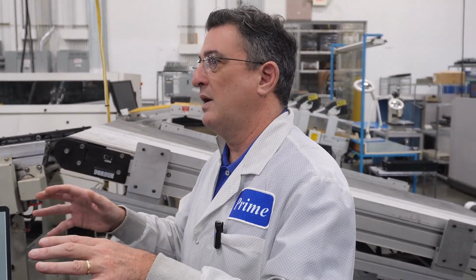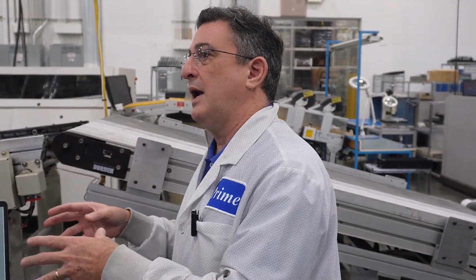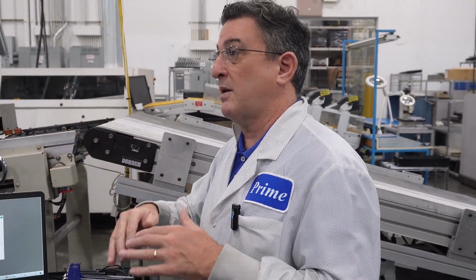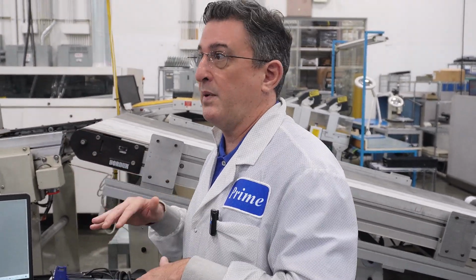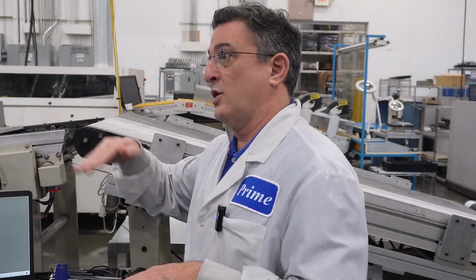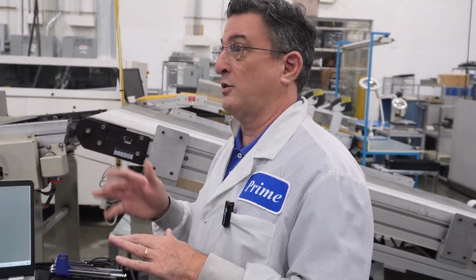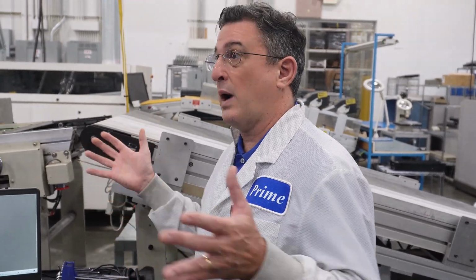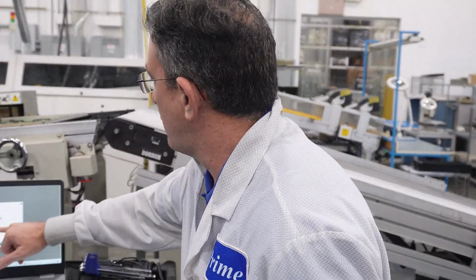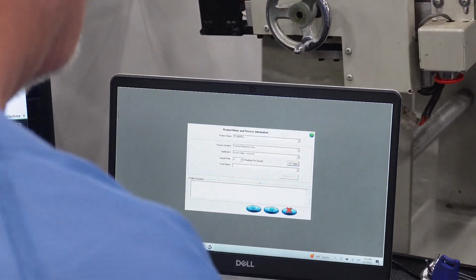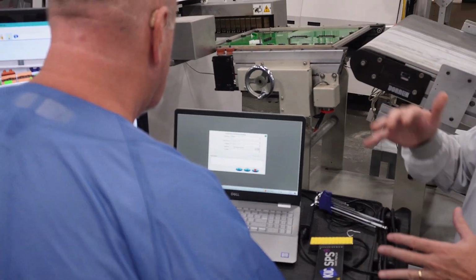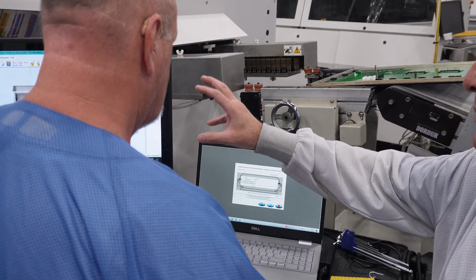A lot of customers call me and say, I got that bad profile thing. And I say, well, the profile's not lost. It automatically saves it to memory and you can export it, email it to me, and I can show you exactly what happened. Sometimes it may need to change those trigger levels, or sometimes it could be a problem with the process equipment itself, introducing temperatures that we didn't expect, that shouldn't be there, that caused that profile to fail. That's why we have that safety mechanism. So I would recommend we just go ahead right now and stay with default. And if we see temperatures outside the norm, then we can go in and change those triggers to meet those needs. Okay. Equipment.